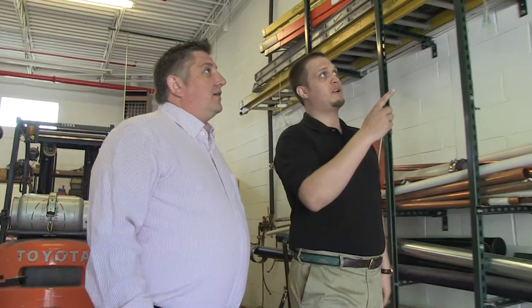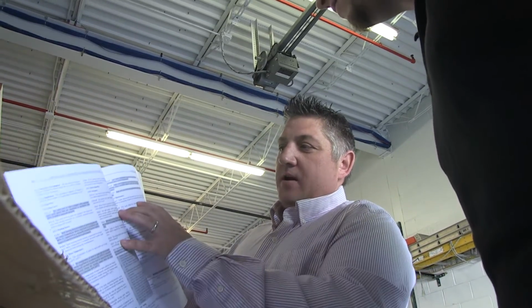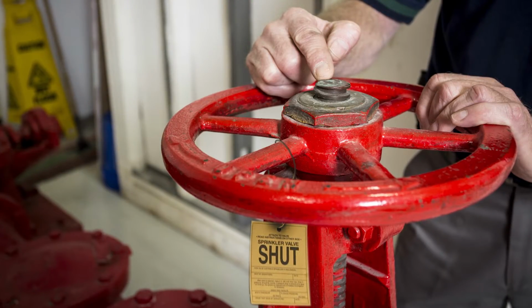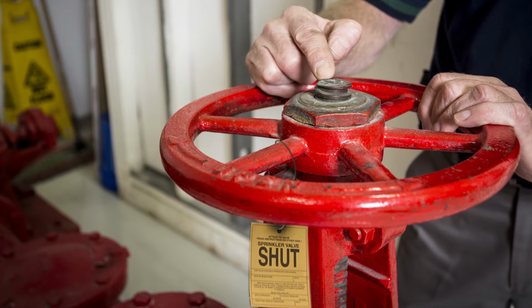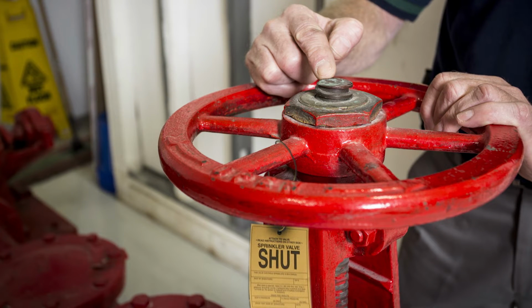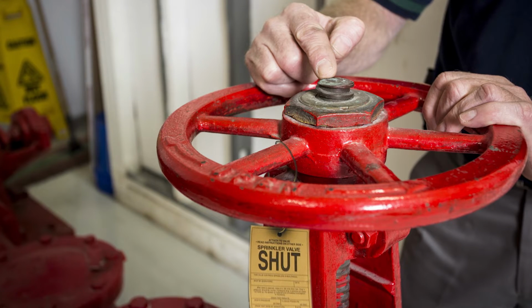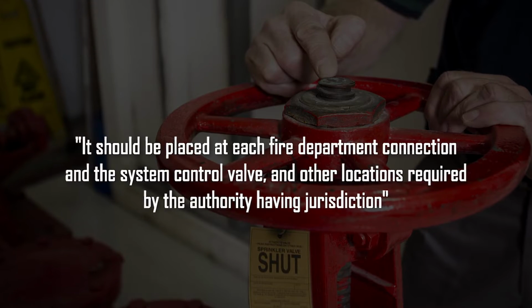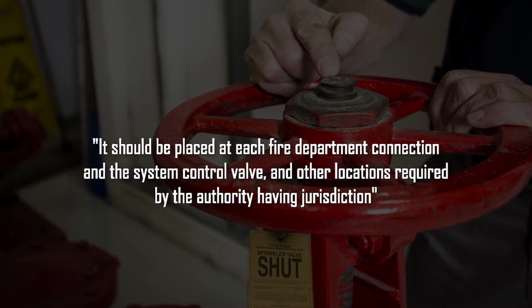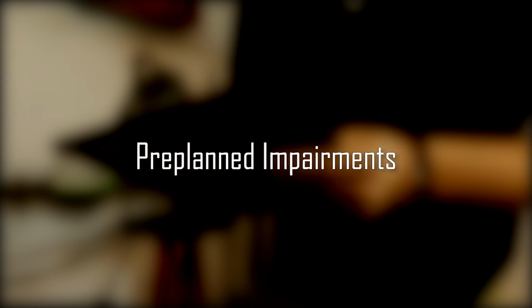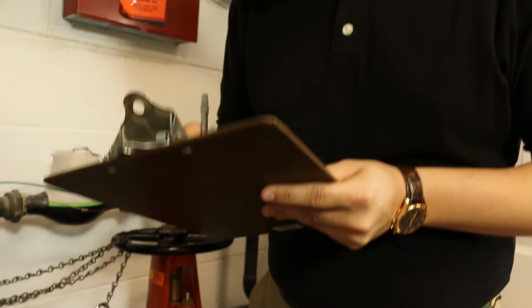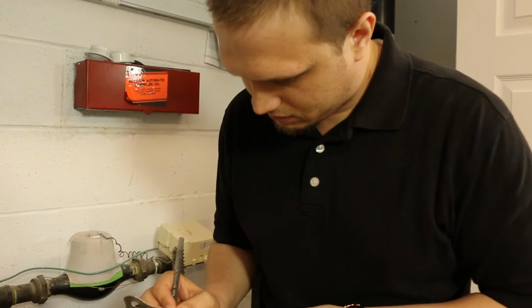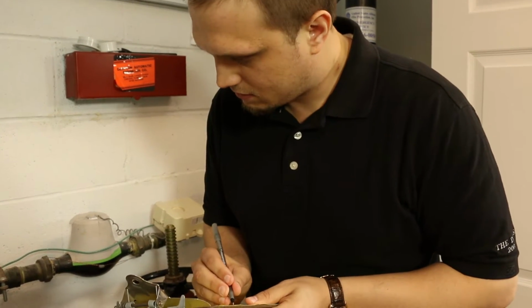You, as the building owner or manager or the designated representative, must assign an impairment coordinator to meet compliance or designate yourself if no one is available. If an impairment to a water-based fire protection system arises, the impairment coordinator must use a tag that indicates what system or part of the system has been removed from service. It should be placed at each fire department connection and the system control valve and other locations required by the authority having jurisdiction. The impairment coordinator must authorize all pre-planned impairments and first verify that the following procedures have been implemented before corrections or repairs begin.